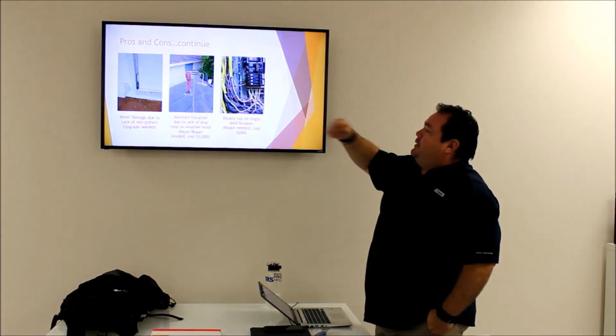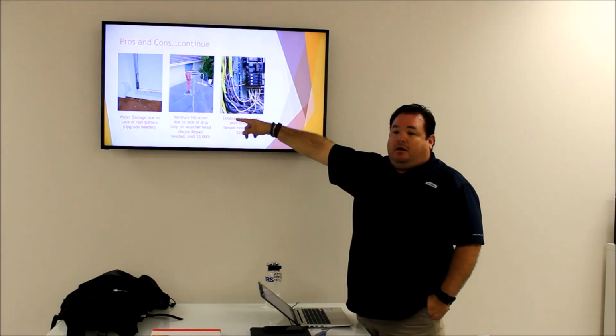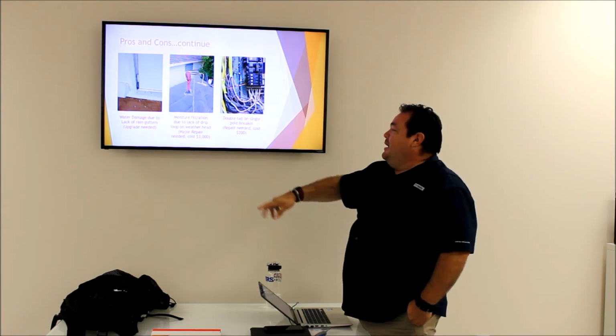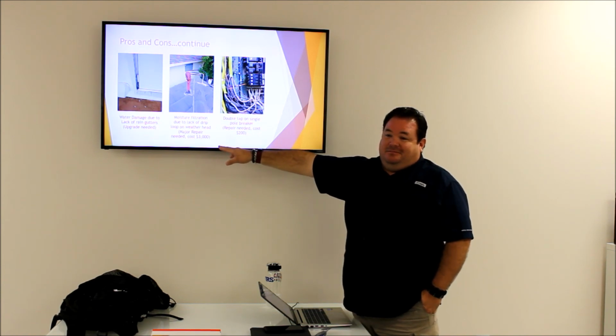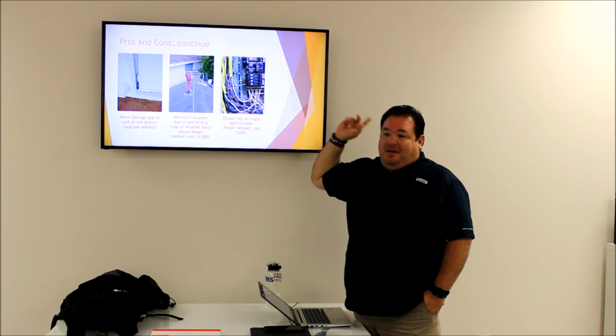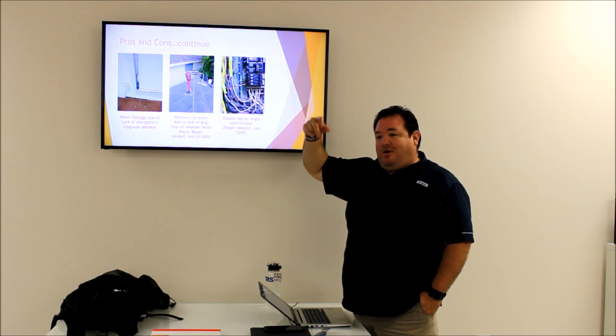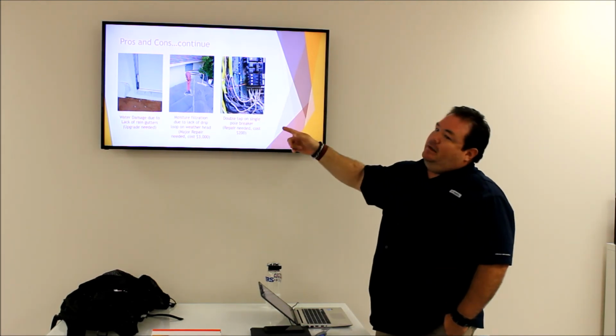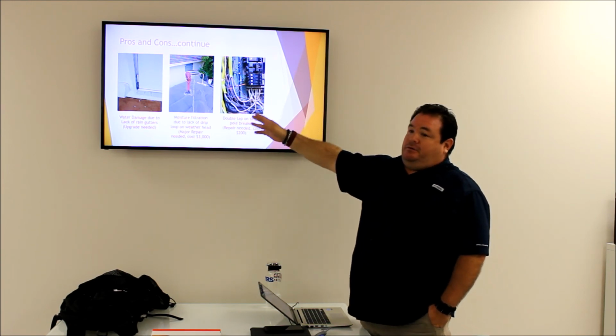In this particular case, guys, water was coming all the way into the main meter of the house. So this is something that took $3,000 to repair. Because you gotta call FP&L to disconnect that main service so an electrician can come and replace the wires and just put a loop to it. Okay? Little things like that. Well, not little things, sorry. That's a major, major thing.